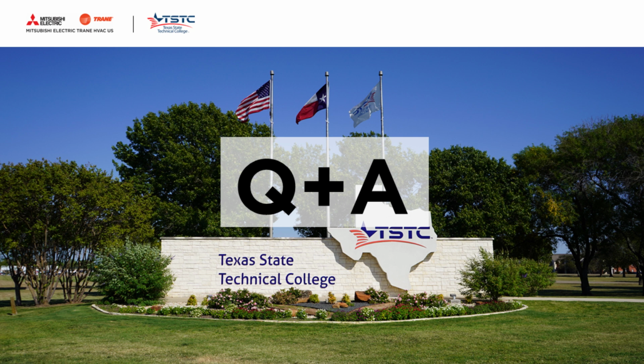John, yes, sir. I would confirm and agree with Jay's statement there. A VRF system can certainly accommodate a setback schedule. A conventional system, if you put it into setback, if you've got a 70-degree comfort set point, and in a heating example, maybe you let the building cool down to 65 or even 60 overnight, or perhaps on a period of break. A VRF system could do just exactly the same thing. When the set point comes back into recovery, when you go from that 60-degree back up to your 70-degree comfort, the VRF system will ramp up high into capacity to meet that set point, but then again, modulate down to just maintain it.